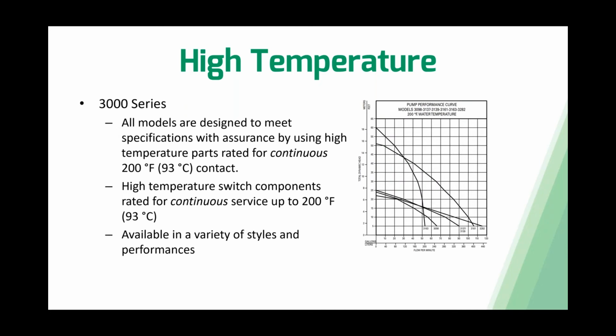Within the 3000 series, it's pretty similar. We offer a couple more options there, but all models are designed to meet specifications with assurance by using high temperature parts that are rated for continuous 200-degree contact. And the same with the switching components, they're rated for continuous service up to 200 degrees. Whereas the 2000 series was more of an intermittent type use, when it's touching 180, 190, getting up to 200, but then going down, the 3000 series can handle continuous 200 degrees Fahrenheit with no issues. Like I mentioned previously, it's available in a variety of different styles of performances. I'll mention here on the pump performance curves, I'm sure many of you are familiar with the 98 and the 137, our 160 series, or 280 sewage series. All of those mentioned are available in a high temperature option.